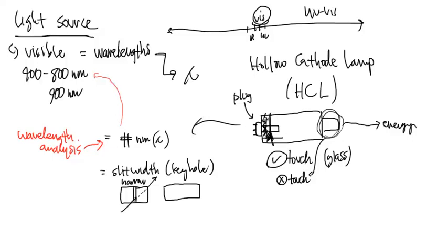so that way it can do its job and fine tune itself in more detail. A wider slit width would basically take that area and open it up a little more so that the lamp light can go through and out the other end, and there's a wider area that's associated with that slit width. They all will have their own settings. You need to make sure that you take a look at that setting, and you have to make sure that your instrument is going to be finely tuned to that setting.